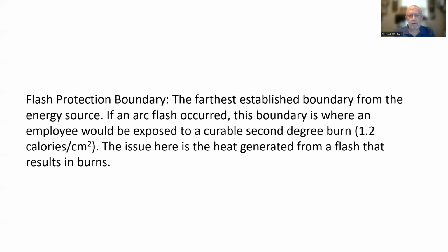The flash protection boundary is the farthest established boundary from the energy source. If an arc flash occurred, this boundary is where an employee would be exposed to a curable second-degree burn, and that's 1.2 calories per square centimeter. The issue here is the heat generated from a flash that results in burns. So they're saying a curable second-degree burn, 1.2 calories per centimeter squared. You're going to hear that figure a lot in arc flash, calories. And when they say cal, they're going to talk about 8 cal. That's 8 calories per square centimeter. Remember, a centimeter is not very big. So 1.2 calories per centimeter squared is what they figure would be a curable second-degree burn.